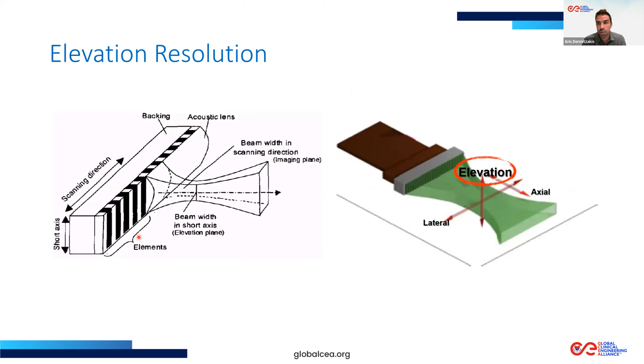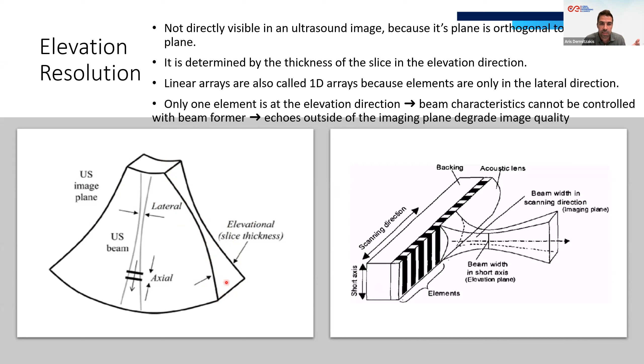And at the end, we have the elevation resolution. The elevation resolution is the resolution in this direction. Now, if you remember, we have an array. In the array, we have elements only, piezoelectric crystals, one next to the other. So in the elevation direction, we have only one crystal. So we cannot have any beam forming, we cannot have any focusing. So we cannot change the thickness of the slice. This is the elevation direction, the elevation resolution, the thickness of the slice.